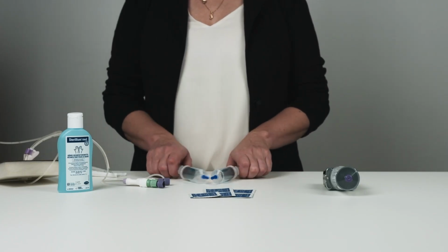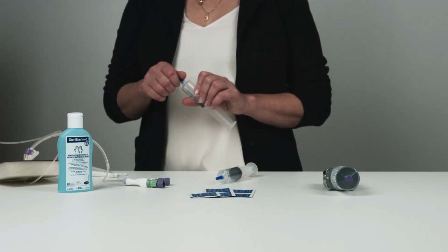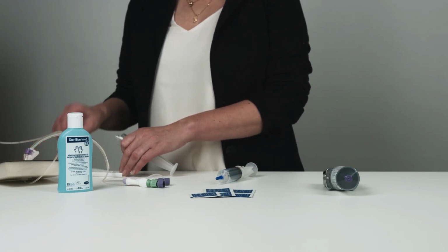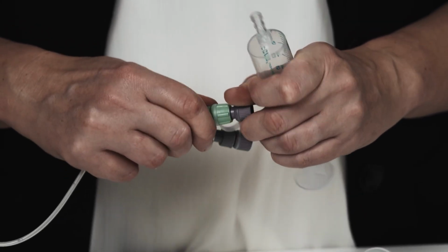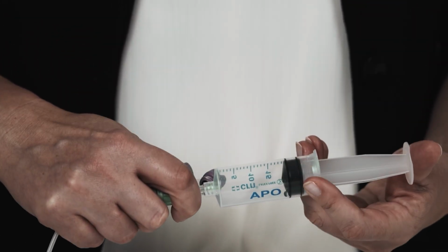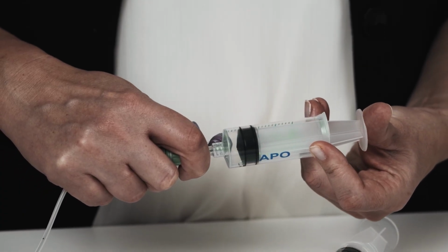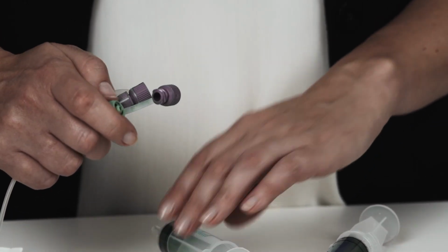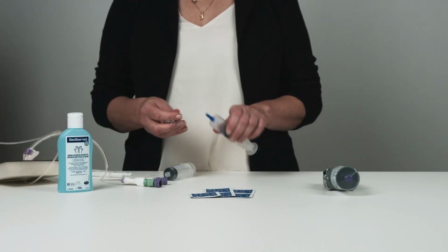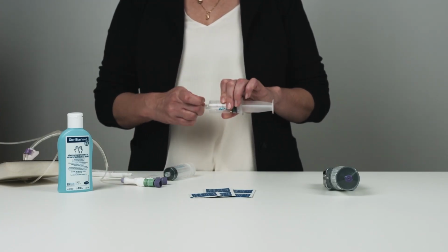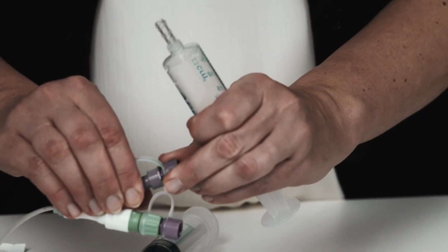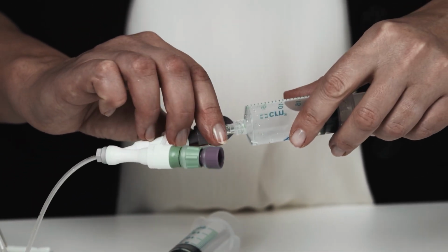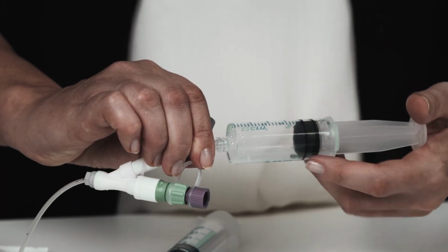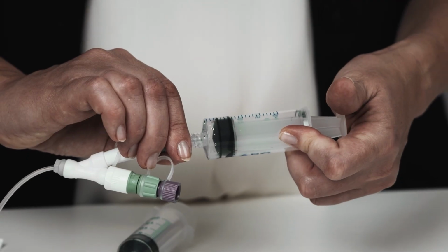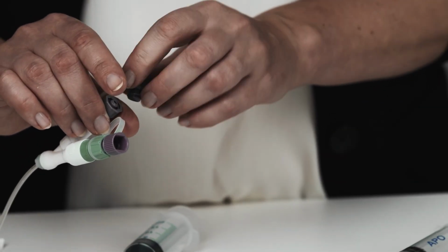Fill 2 20 ml ENFit syringes with tap water and have the adapter for the gastric port ready. Open the intestinal port. Insert the syringe and press the plunger with constant, moderate downward pressure to flush the probe. After flushing, remove the syringe and close the intestinal connection. Now place the adapter for the stomach port onto the other syringe. Open the stomach port, insert the second syringe and press the plunger with constant moderate pressure to flush the probe. After rinsing, remove the syringe and close the stomach port.